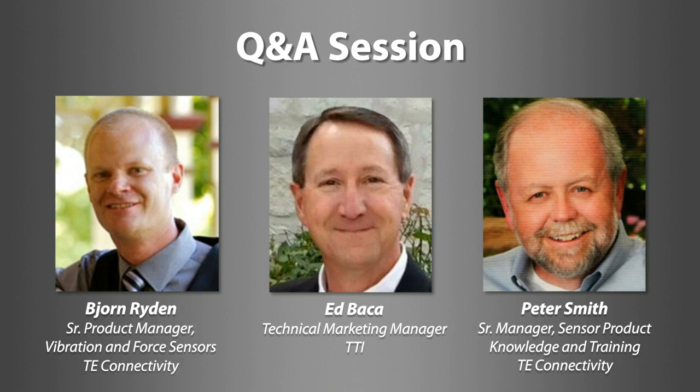Okay, so yes, the question is correct. The sensors that we have shown in this presentation are small board-mountable chips. There is a piezoelectric ceramic PZT crystal inside, and then a charge converter. So you're getting a raw analog voltage output signal from the device. In order to determine what that signal means, you're going to have to do post-processing. And it really depends on what type of machinery you're monitoring. The intelligence needs to be in your data acquisition or your post-processing of the signal in order to determine what events to look for.